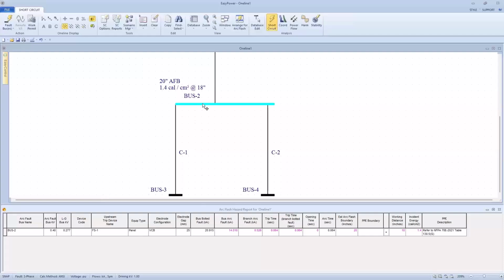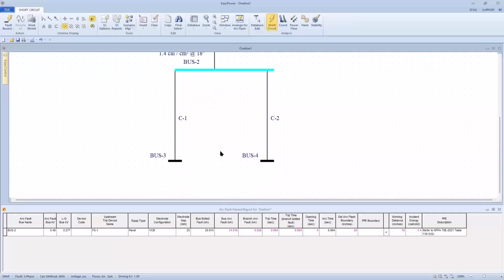If I look at the calculations for the secondary of the transformer, it's a 480 volt bus. The fuse is a protective device. We define the equipment as a panel with vertical electrode configuration, an electrode gap of 25 millimeters. We already knew the bolted fault current. The arc flash current, according to the model, is 14,018 amps. The branch current through the fuse is 526 amps. At that current, the fuse will blow in 64 milliseconds. Put all that into the IEEE equations, we get 1.4 calories per square centimeter at a working distance of 18 inches.